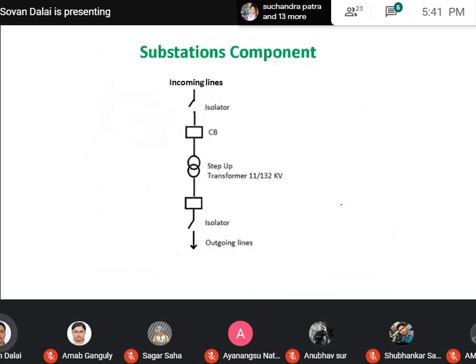So these are the different components present, and this is the line diagram of the different components. One of the major components is the transformer, which may be step up or step down depending upon the voltage level. So this is the picture where the generating voltage level is stepped up to 132 kV. So this is the step up substation, but if it is a distribution substation, then instead of a step up transformer, this should be a step down transformer where the voltage level is converted from 132 kV to 11 kV. But otherwise, they consist of similar components.